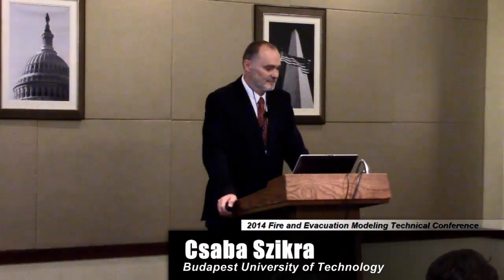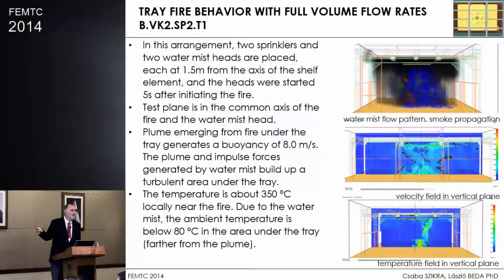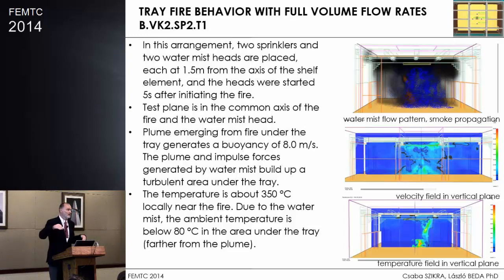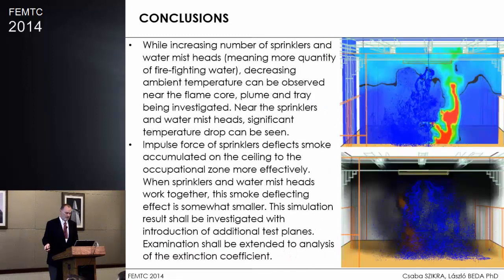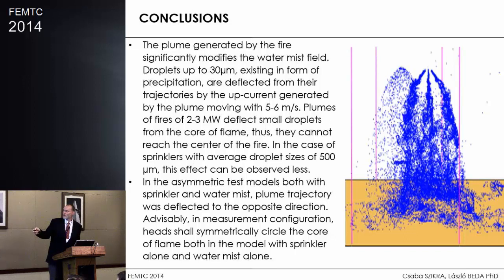Audience question: Could you go back to some slides and describe which one was the sprinkler and which was the water mist? In my experience, water mist is typically volumetric filling and both of those looked very similar. Presenter: It's symmetrical — the two in one pair are sprinklers and the two in the other pair are water mist. In the section view, this would be the sprinkler and this would be the water mist — you can see it has more spread heads, that's why it looks like that.